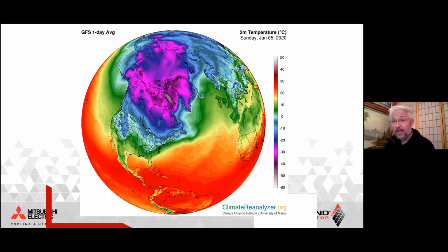I mean, that was an extreme event, but I didn't really get any complaints this past winter or the prior winter. And let me tell you, if somebody was going to pick up the phone and complain about their heat pumps, I would be that guy that would get that phone call from the sales reps or the contractors or anybody else. But it just doesn't happen. And part of the reason that people are concerned about this is because traditionally heat pumps really weren't designed to operate at really low temperatures. They either didn't have a refrigerant that had these super cold capabilities to have a really low boiling point, or they didn't have compressors that could spin up to very high RPMs.